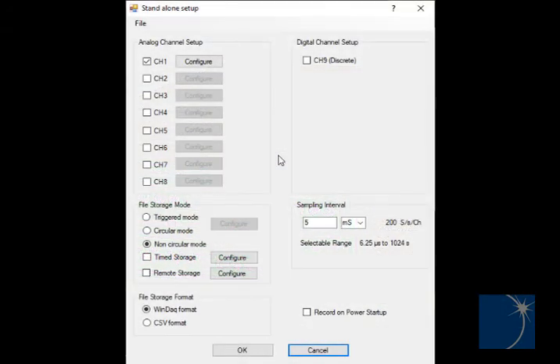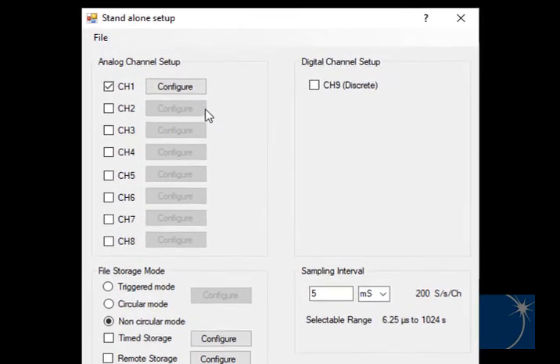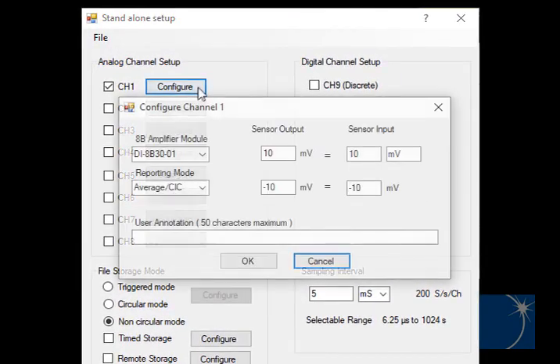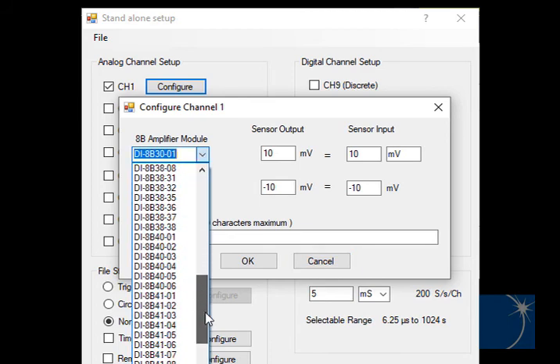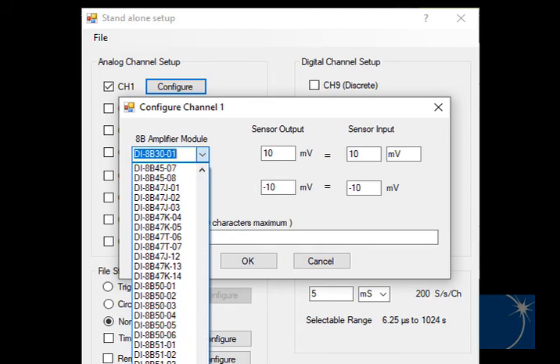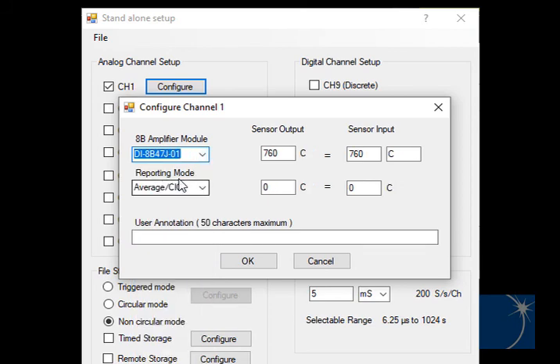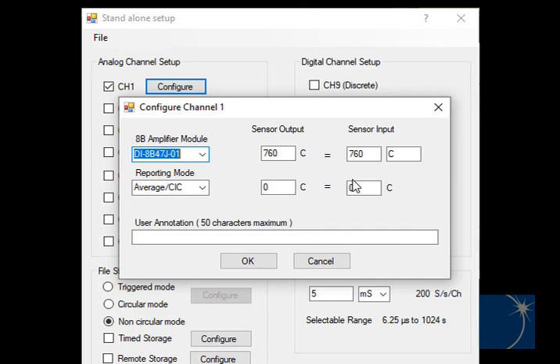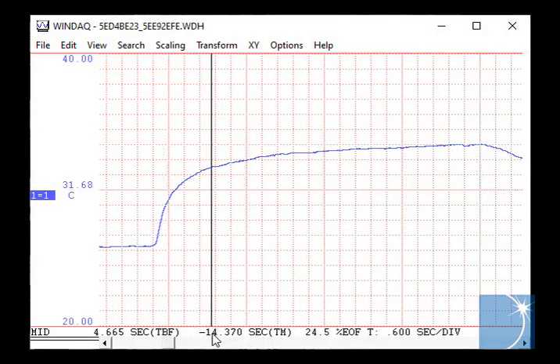Designed to accommodate DI-8B series signal conditioning modules, scaling channels to display engineering units is as simple as choosing the appropriate signal conditioning module from the DI-8B amplifier module pull-down menu. In this example, a DI-8B47J-01 thermocouple module. As you can see, upper and lower level sensor output and sensor input levels are automatically populated, so information recorded to the USB flash drive in stand-alone mode is in meaningful units.